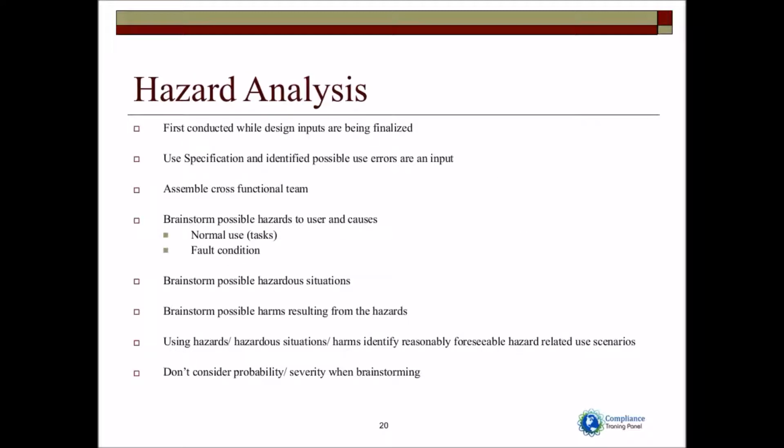The hazard analysis is first conducted while the design inputs are being finalized. And again, for the reason that you want to be able to factor the results into the requirements and early into the design. The use specification and the possible use errors that were identified earlier are an input to the hazard analysis.